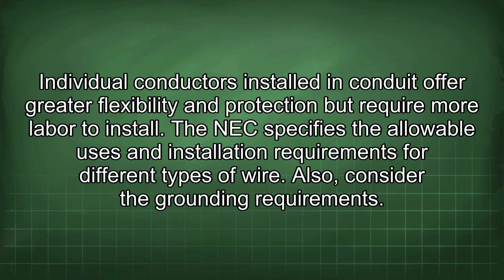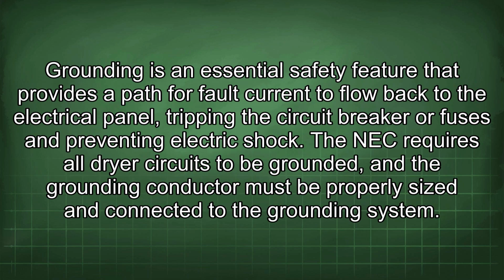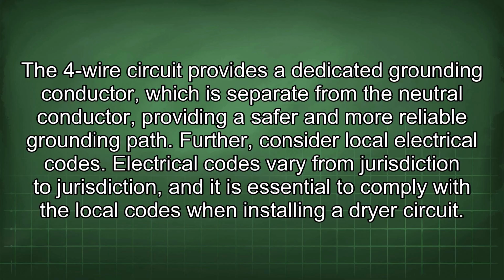Also, consider the grounding requirements. Grounding is an essential safety feature that provides a path for fault current to flow back to the electrical panel, tripping the circuit breaker or fuses and preventing electric shock. The NEC requires all dryer circuits to be grounded, and the grounding conductor must be properly sized and connected to the grounding system. The 4-wire circuit provides a dedicated grounding conductor, which is separate from the neutral conductor, providing a safer and more reliable grounding path.